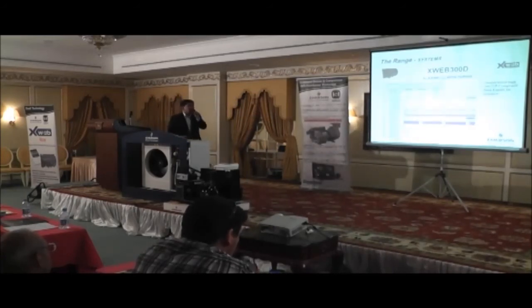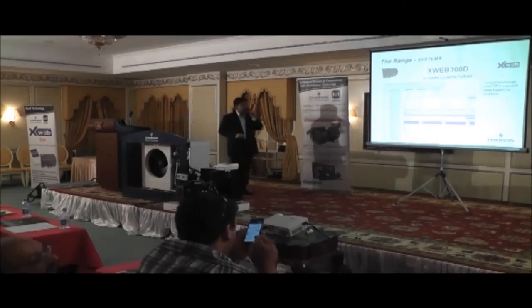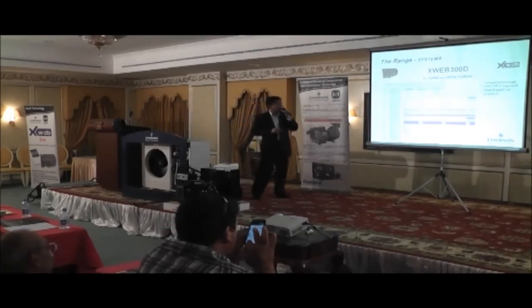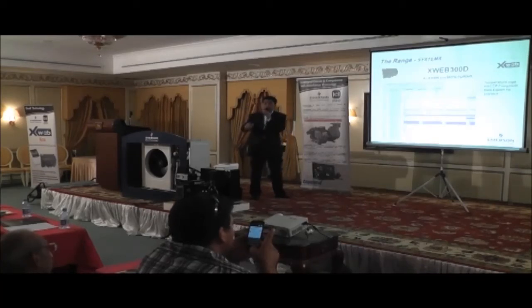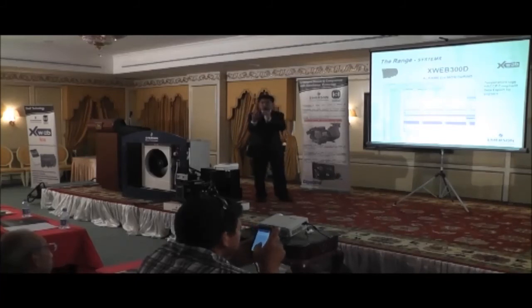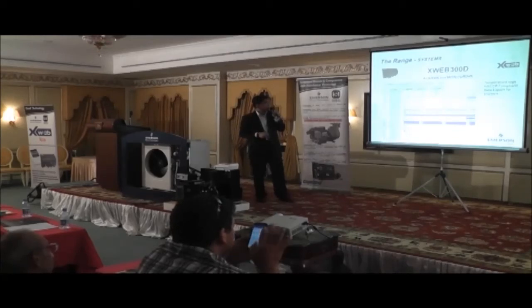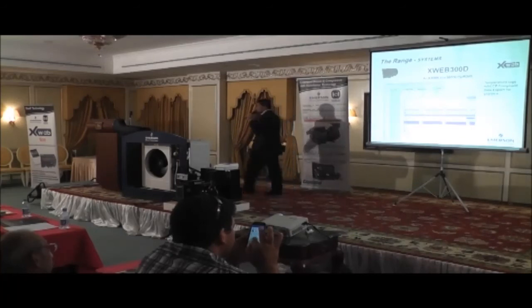And this is the example of the data reading. So you have the date, you have the time, and these are the temperatures. You can configure which type of temperature you want. You want the set point, you want the evaporator temperature, and the room temperature. And this is also the graph that shows the status of the unit. It will easily show you some peak of temperature, for example.